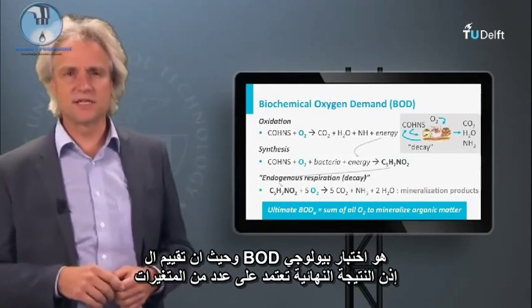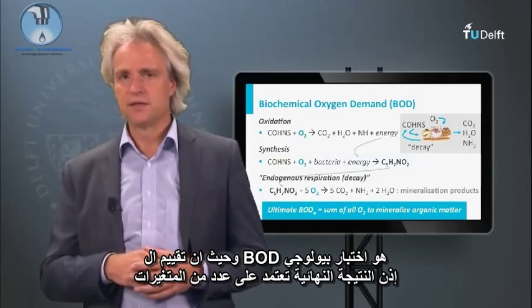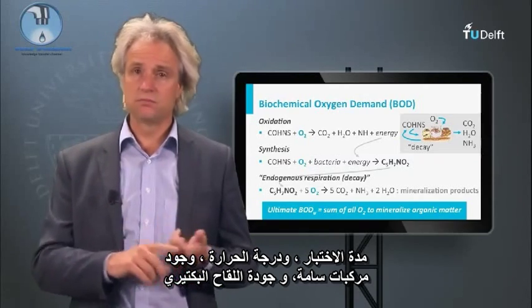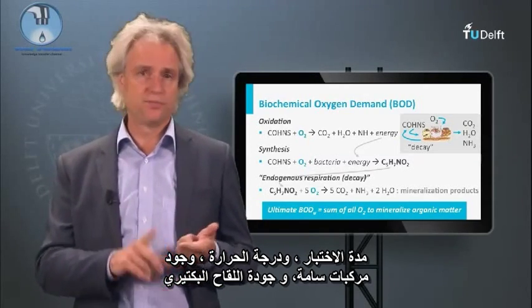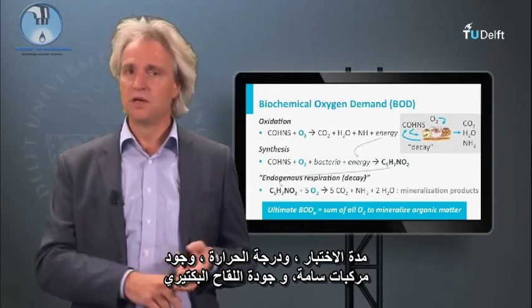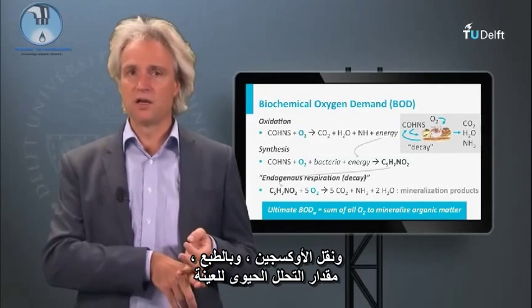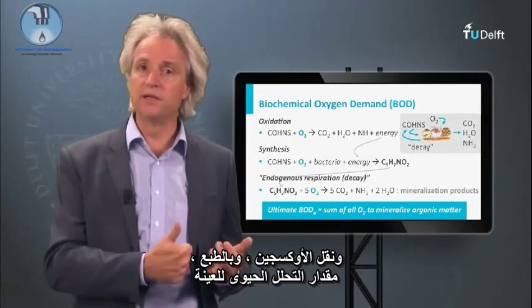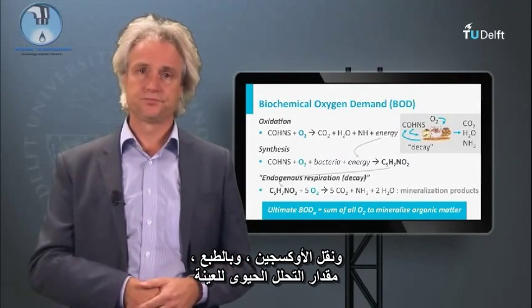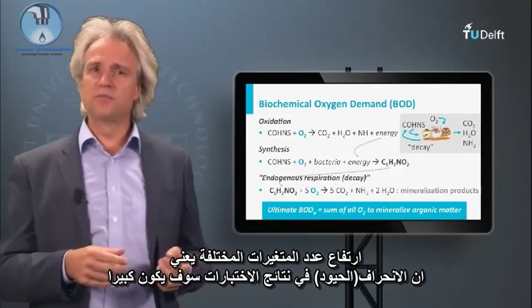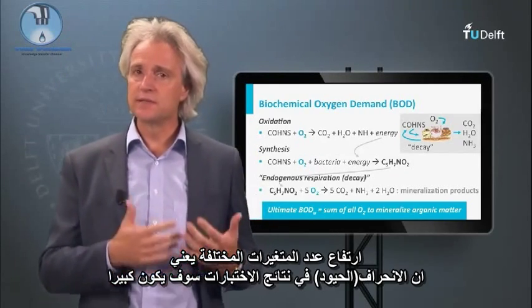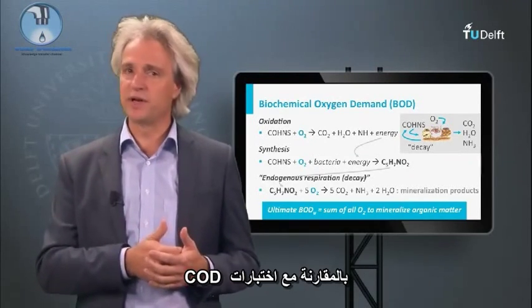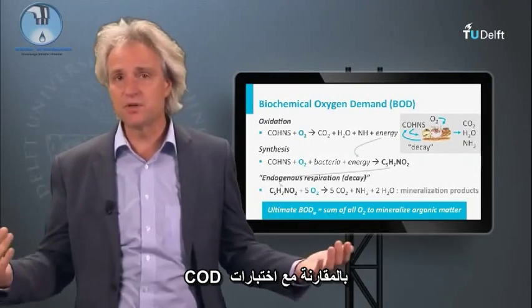Since a BOD assessment is a biological test, the final result depends on a number of parameters: test duration, temperature, the presence of toxic compounds, the quality of the bacterial inoculum, the oxygen transfer, and of course the biodegradability of the sample. The high number of variable parameters means that deviation in test results will be much larger compared to the COD test, which is a chemical test.